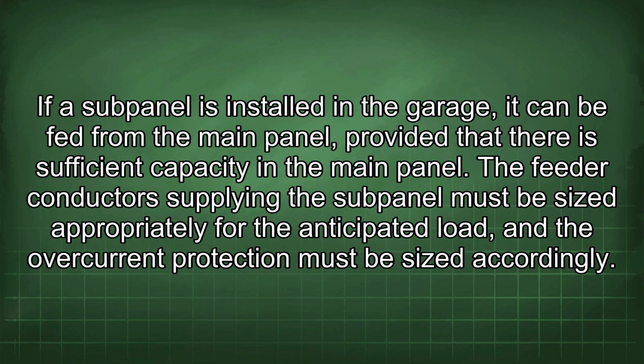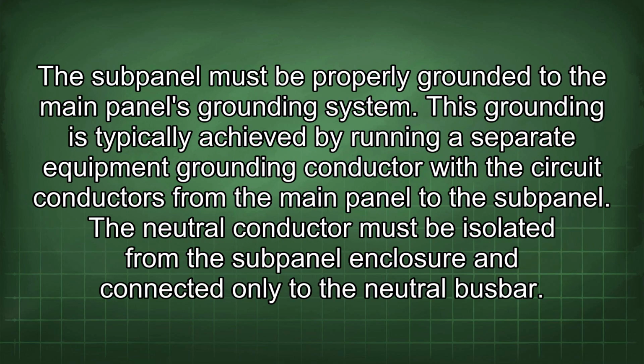If a subpanel is installed in the garage, it can be fed from the main panel, provided that there is sufficient capacity in the main panel. The feeder conductor supplying the subpanel must be sized appropriately for the anticipated load, and the overcurrent protection must be sized accordingly. The subpanel must be properly grounded to the main panel's grounding system. This grounding is typically achieved by running a separate equipment grounding conductor with the circuit conductors from the main panel to the subpanel. The neutral conductor must be isolated from the subpanel enclosure and connected only to the neutral busbar.